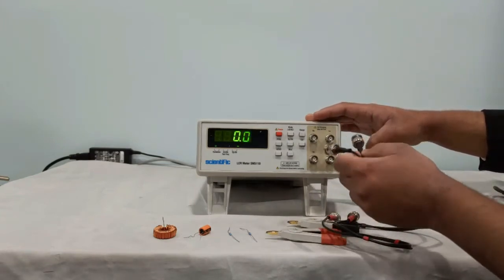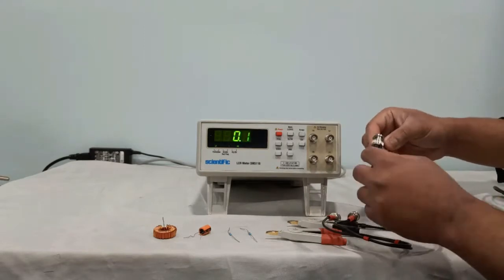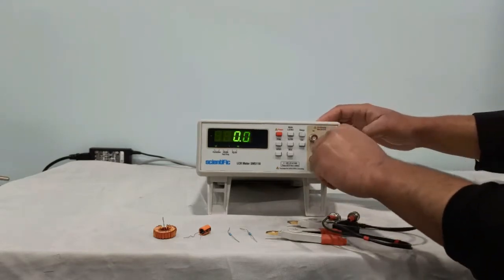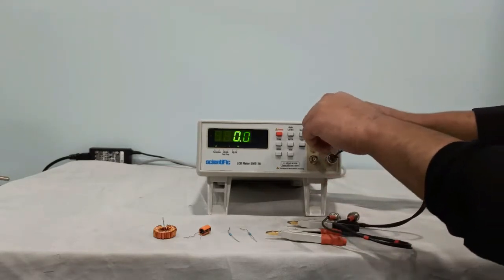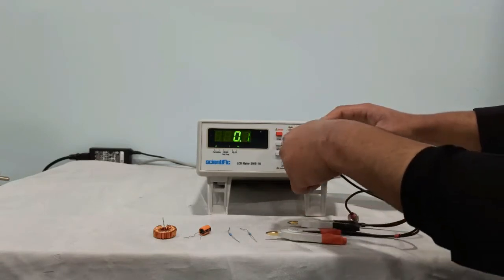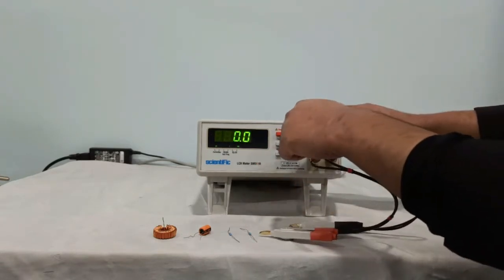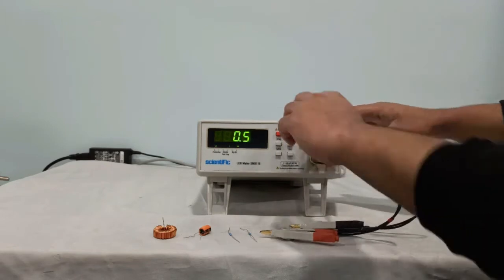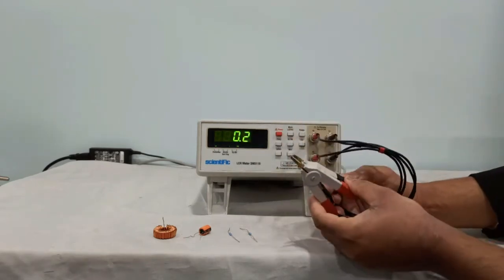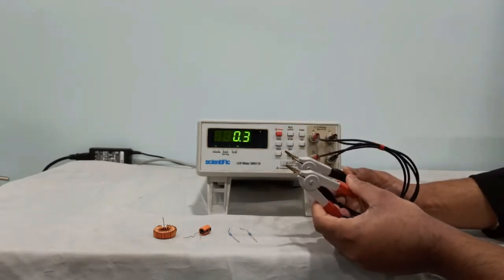We need to connect this Kelvin probe to the BNC connectors. Black will go to LS and LD, and red connectors will go to HS and HD. This is how we connect the Kelvin probe. These are the two terminals where you can connect your DUT.